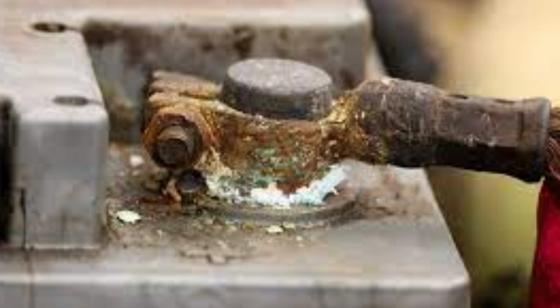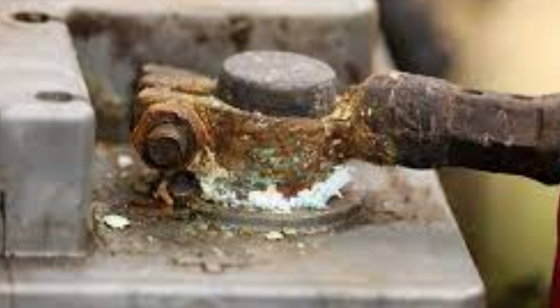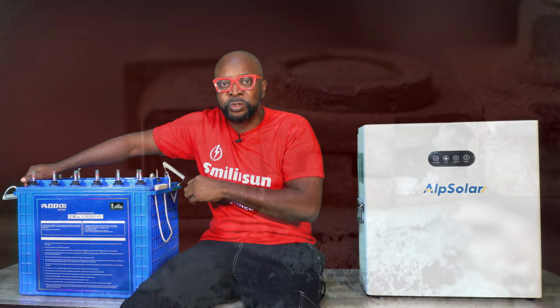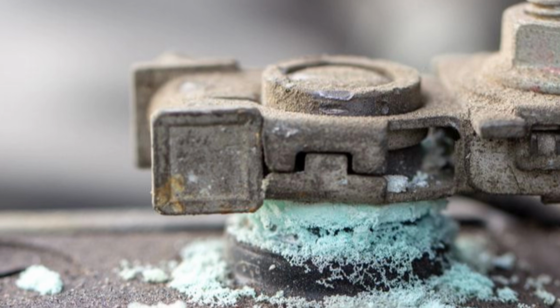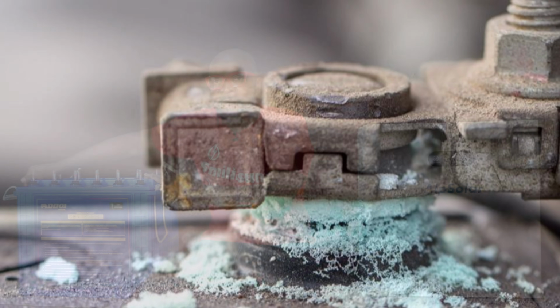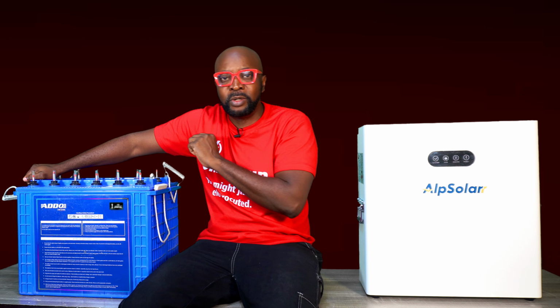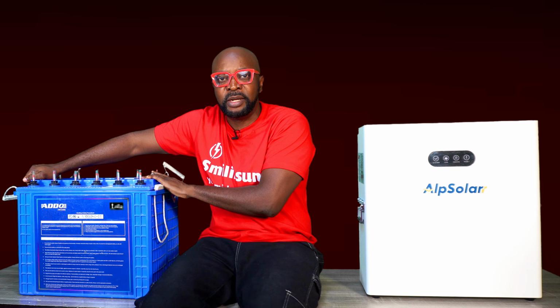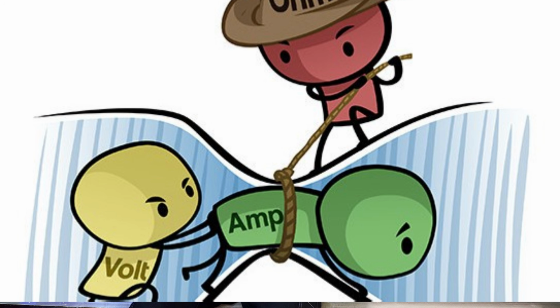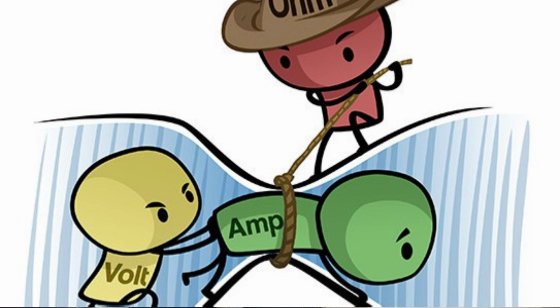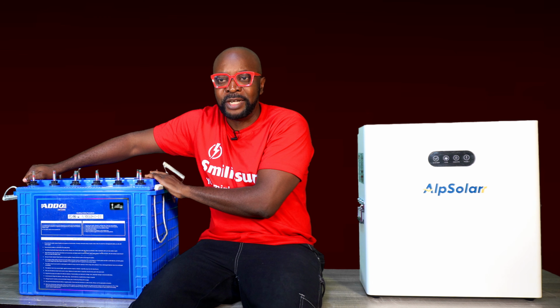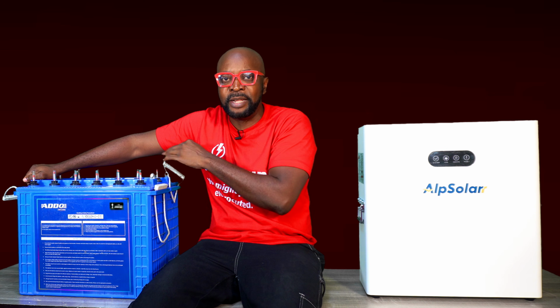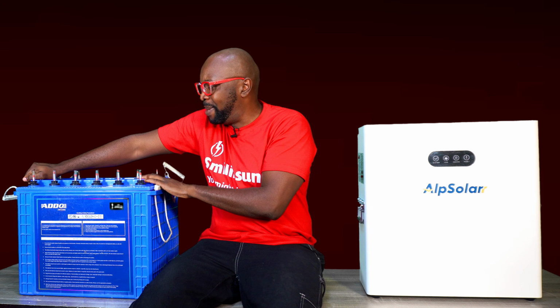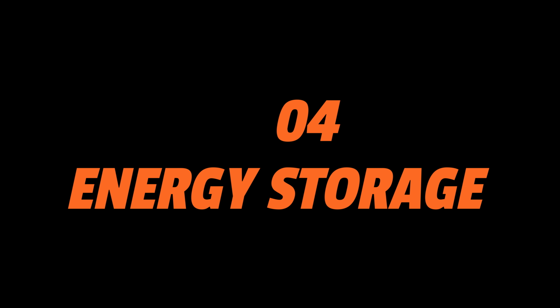So at some point, you might need to service the batteries, completely shut down your system, loosen the bolts, clean it up. You can also use sandpaper at some point to clean it up. Because if you don't take off that corrosion on the terminal of the batteries, it is going to form resistance in the batteries. You might have resistance in the current flow in the battery, which is what you don't need because you need the energy to be flowing unabated.